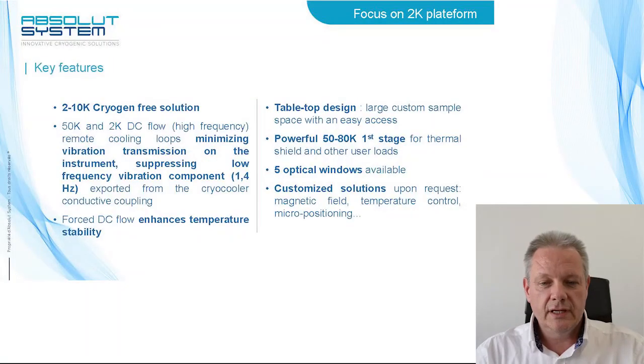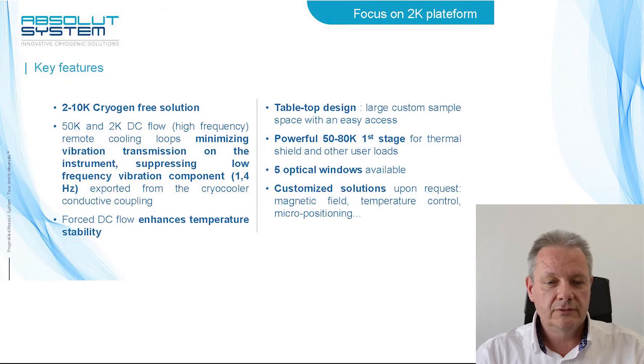The 2K XCube platform is a cryogen-free solution with no liquid nor gas consumption. It provides 50K and 2K forced flow loops, minimizing the vibration transmission to the application and suppressing the low frequency 1.4 Hz exported from the cryocooler conductive coupling, which is very difficult to damp. Moreover, DC flow enhances the temperature stability compared to the low frequency temperature sweep of the cryocooler. The tabletop design provides a large custom sample space for the user with easy access.